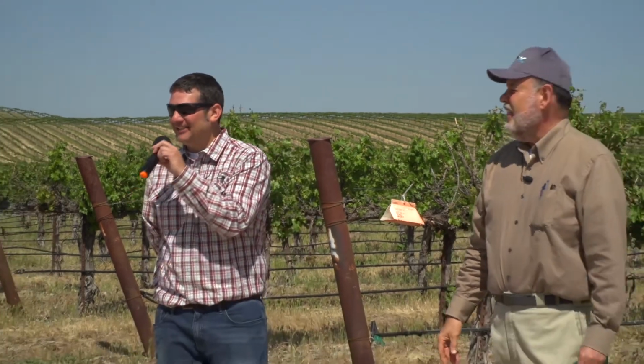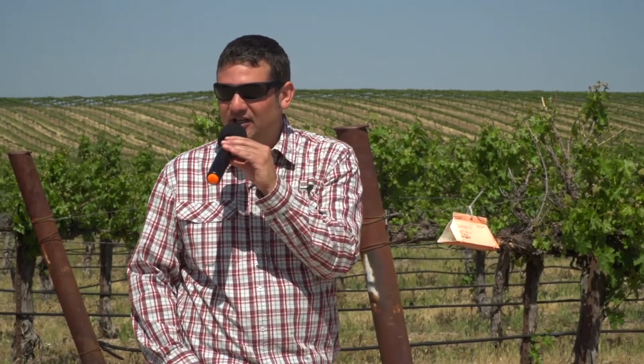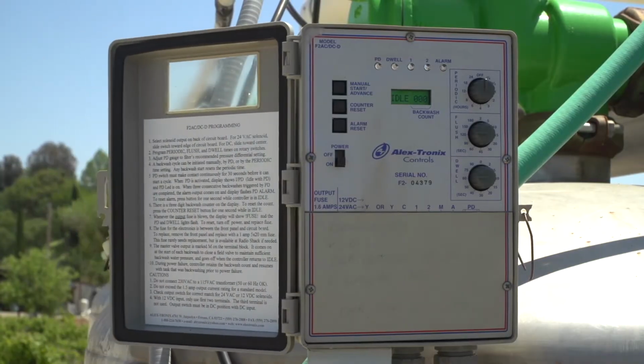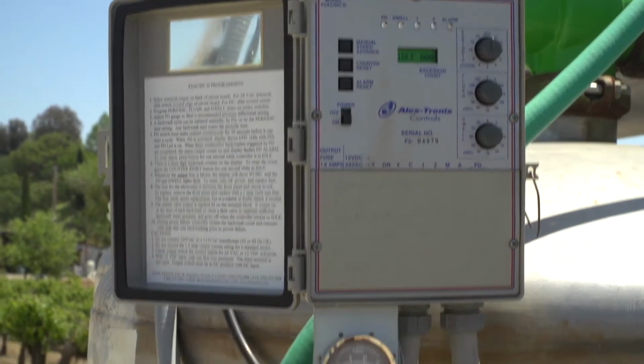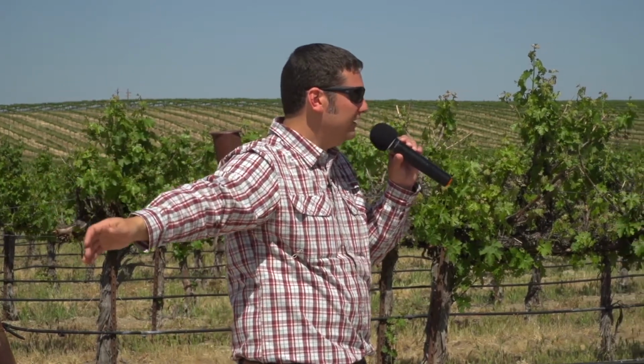Yep. That's next. So, like Craig's saying, the pressure at those filters is another indicator that you might need to be checking your screens or cleaning your media a little bit. The gray box on the end of this sand filter closest to me, that's the backflush detector. It's monitoring pressure for the in and outlets of those filter gauges. It's looking at the differential, and when that differential hits its predefined rate, it's going to give a backflush to that system. Sometimes I don't see those out there, and that's going to ding you.